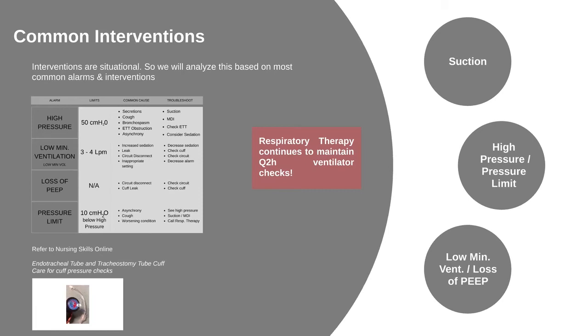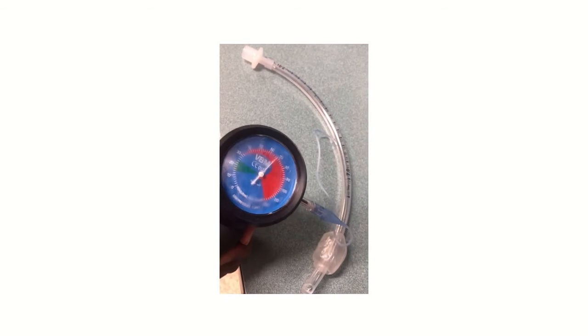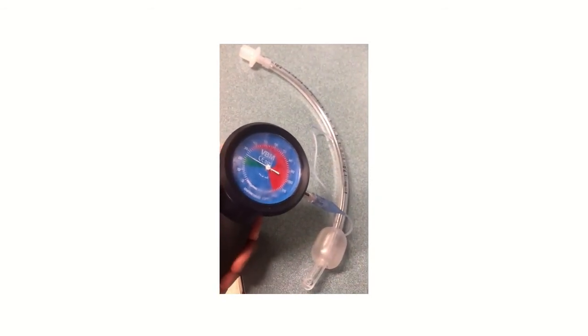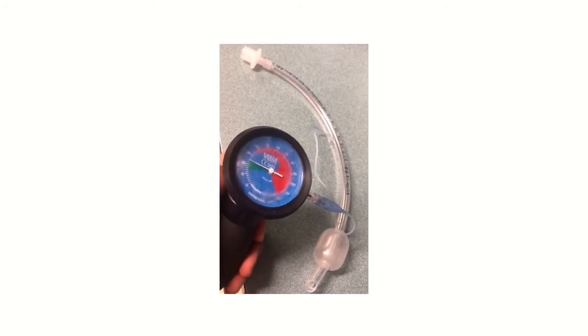One common cause, and therefore troubleshooting step, is to check your cuff pressure. Make sure that you do not have a leak. And here's a short video that actually shows how we check a cuff pressure.